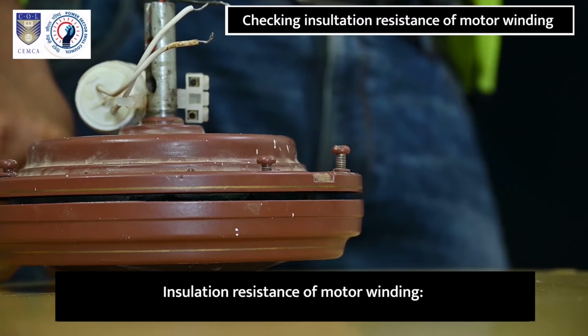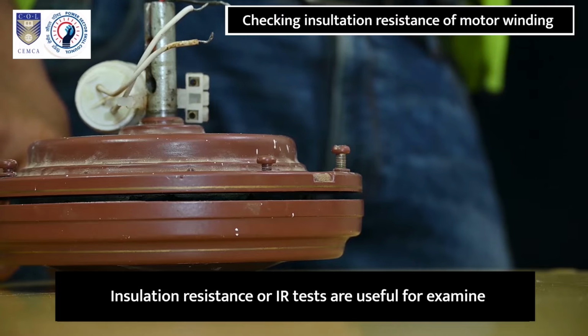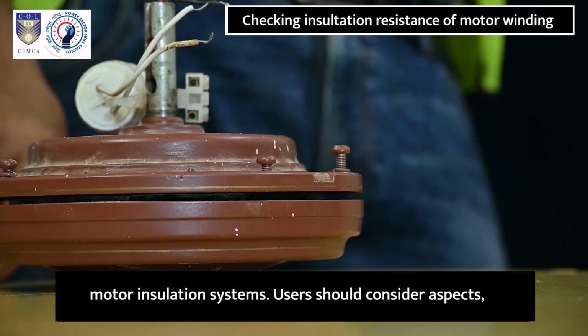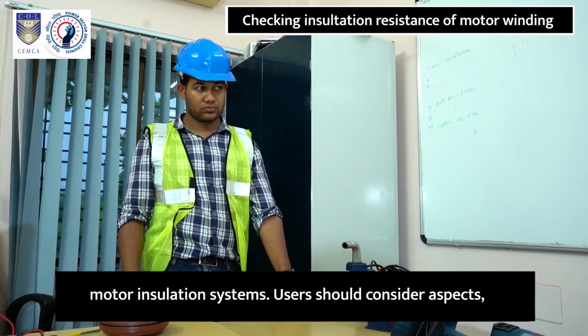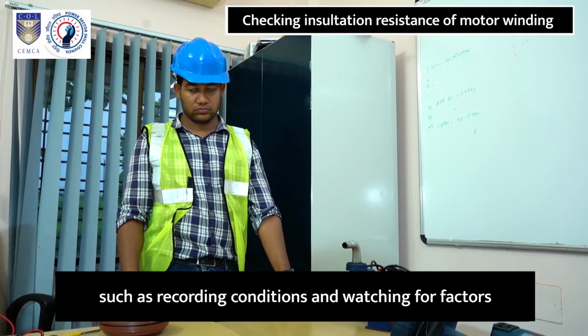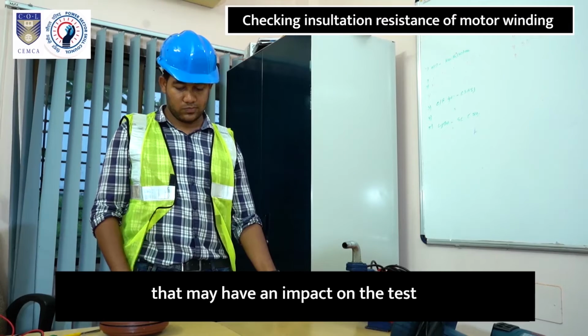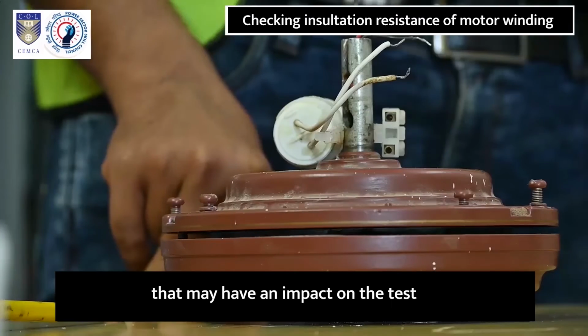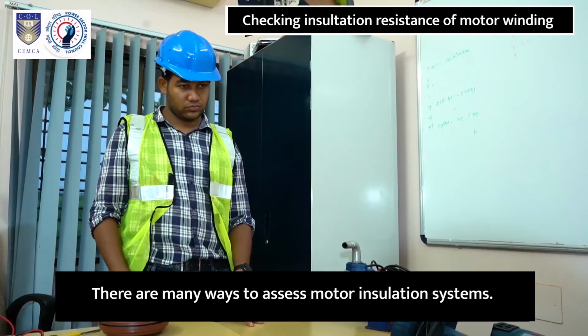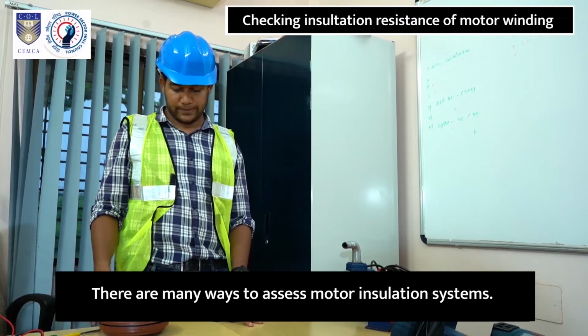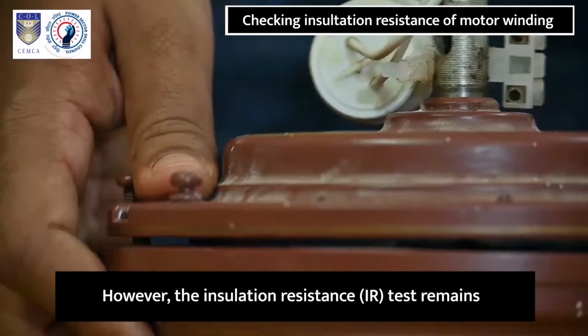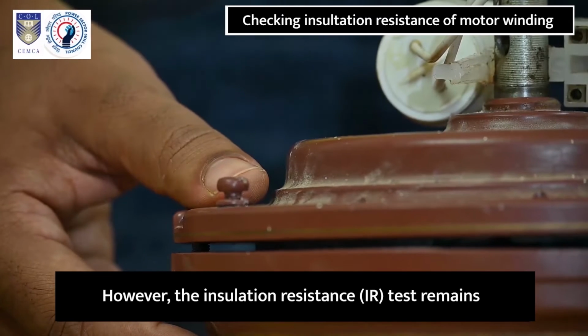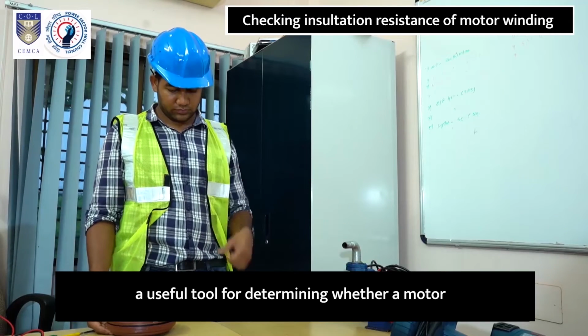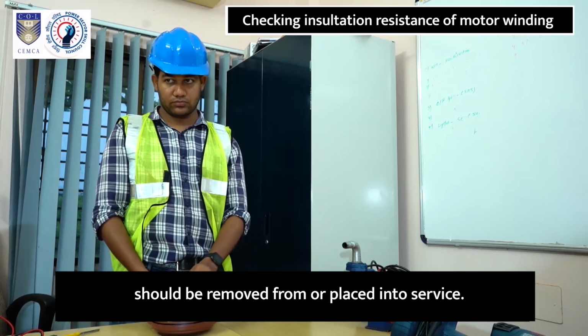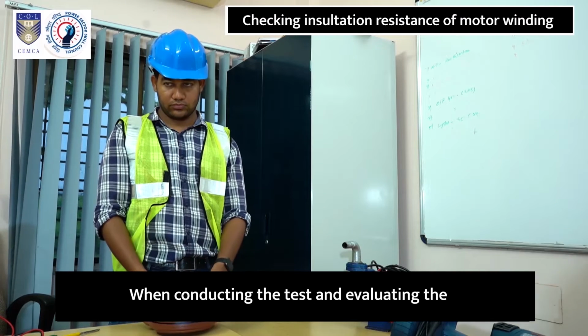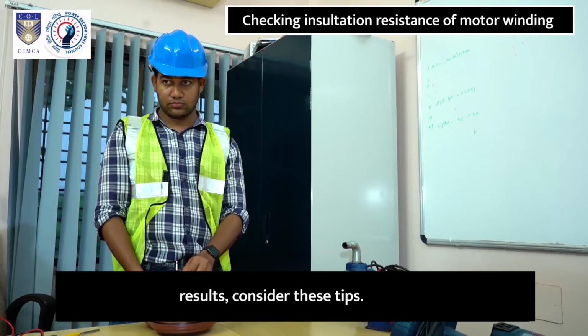Insulation resistance of motor winding. Insulation resistance or IR tests are useful for examining motor insulation systems. Users should consider aspects such as recording conditions and watching for factors that may have an impact on the test to ensure maximum accuracy. There are many ways to assess motor insulation systems. However, the insulation resistance IR test remains a useful tool for determining whether a motor should be removed from or placed into service. When conducting the tests and evaluating the results, consider these tips.